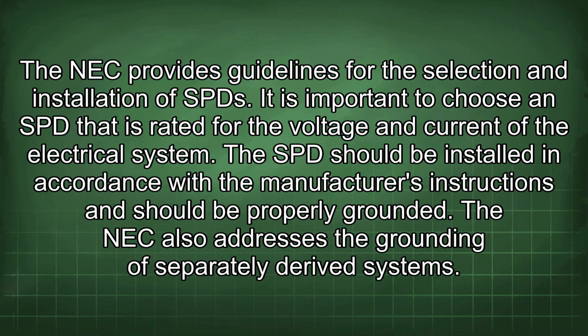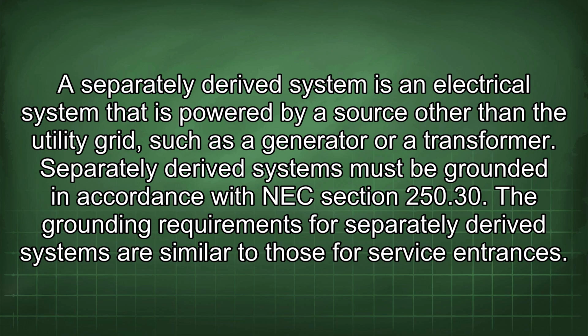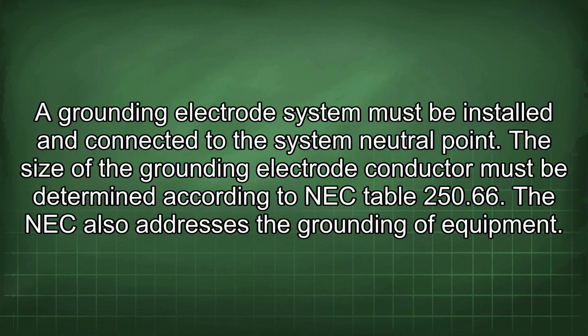The NEC also addresses the grounding of separately derived systems. A separately derived system is an electrical system that is powered by a source other than the utility grid, such as a generator or a transformer. Separately derived systems must be grounded in accordance with NEC Section 250.30. The grounding requirements for separately derived systems are similar to those for service entrances. A grounding electrode system must be installed and connected to the system neutral point. The size of the grounding electrode conductor must be determined according to NEC Table 250.66.